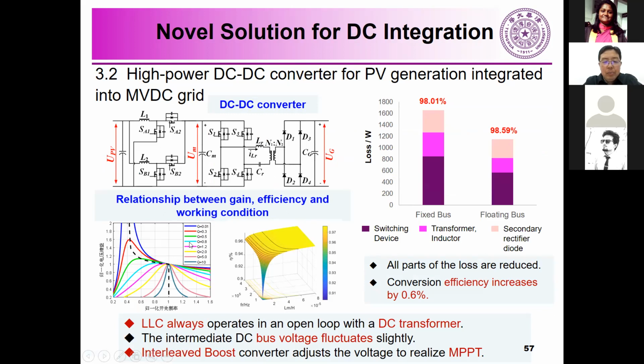Typically the LLC always operates in an open loop, similar to a DC transformer, without voltage regulation, so the intermediate DC bus voltage fluctuates slightly. We adjust the voltage of the PV panels to realize MPPT using this floating bus technology, which allows us to achieve very high converter efficiency.